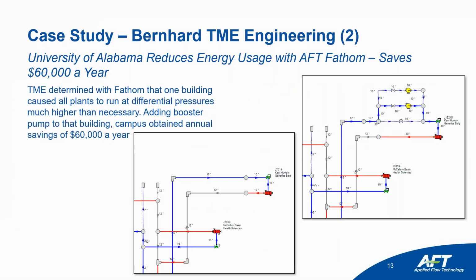So what they found when they were modeling their system is that one of their buildings right here was taking out a much higher than necessary pressure loss, and so it was starving the whole rest of the system. What they recommended was to incorporate a booster pump for that building. That allowed all the rest of the buildings to operate a lot more efficiently, again saving $60,000 a year. But again, don't just pay attention to the energy costs that they're saving there. In addition to saving the energy costs, they've prevented equipment failures and prevented expensive repair costs. That's really what you're doing, by allowing your pumps to operate more efficiently.